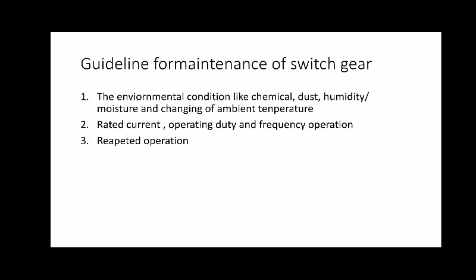Okay, so we want to take proper regular maintenance of all these things, periodic maintenance, periodic inspection of all these things. If there is a periodic inspection, then all those equipments are in proper working condition, so maintenance is done as per the instructions given by the manufacturer. And if there is continuous inspection, continuous maintenance taking place, then the repeated operation or the operation of all the equipment is made proper. We know that in a number of devices there are moving parts, but in a circuit breaker there is one moving part.